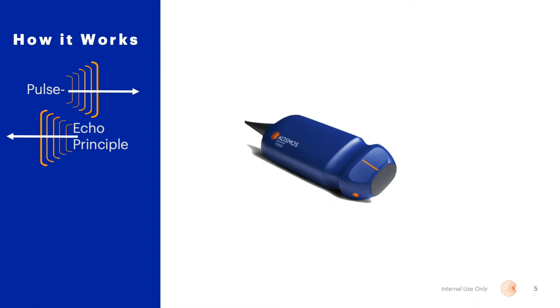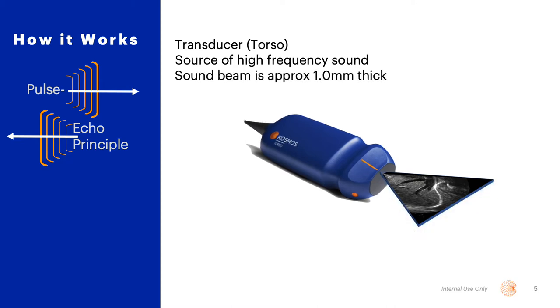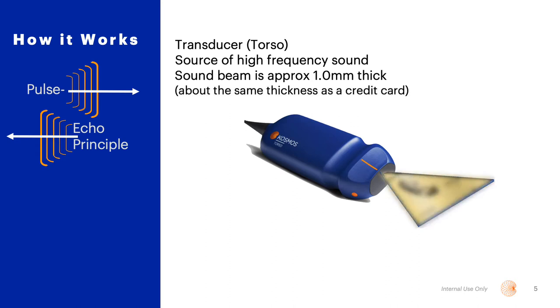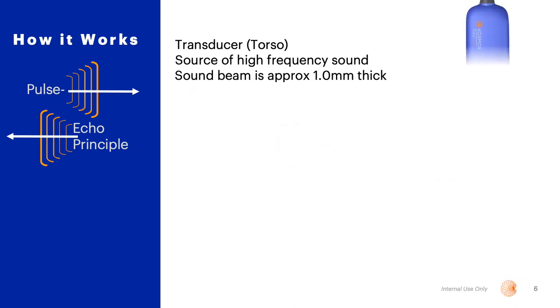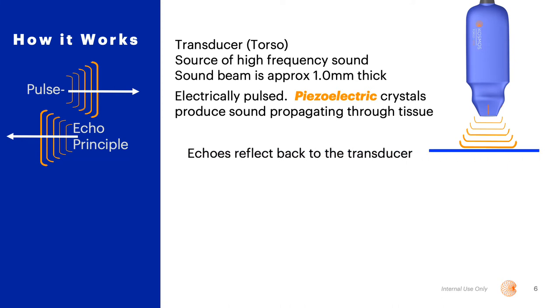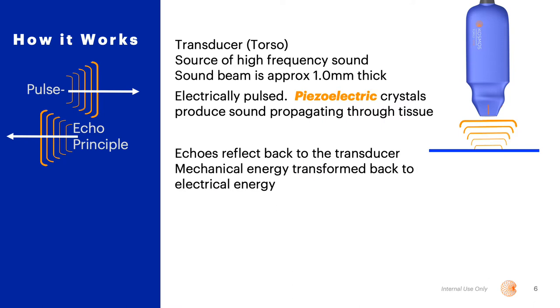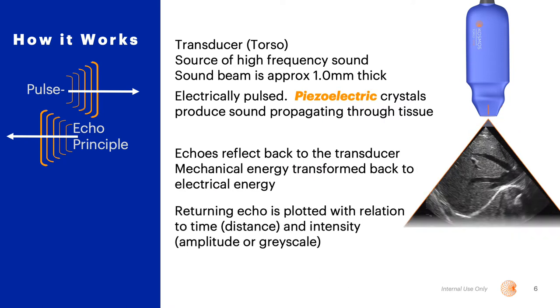Ultrasound works on something called the pulse echo principle. The transducer is the source of the high frequency sound, and while we might think it emits a large block of acoustic energy, the reality is the sound beam is approximately 1 millimeter in thickness, or about the same thickness as a credit card. The transducer is electrically pulsed, the piezoelectric crystals produce sound which propagates through the tissue. Those echoes reflect back to the transducer, the mechanical energy is transformed back into electrical, and the returning echo is then plotted on the screen with relationship to time and intensity.